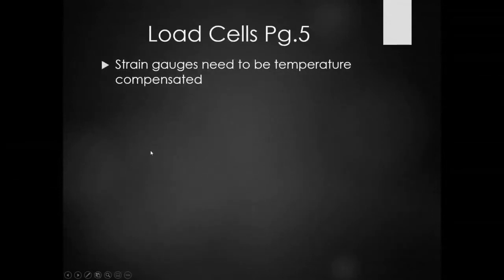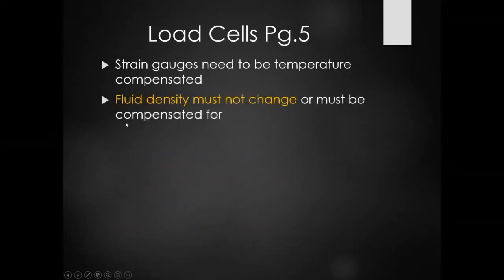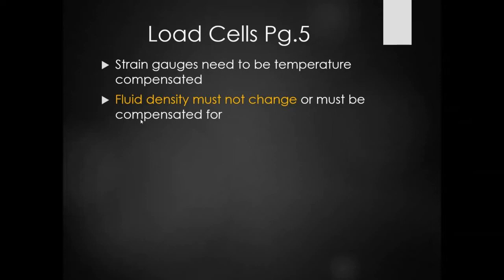Strain gauges, like most resistance-type devices, need to be temperature compensated. The fluid density must not change — this is pretty critical. If we're filling a vessel and the fluid becomes lighter, the level would have to be higher to make the same reading, and if the density were higher, the level would have to be lower. So we have to be sure the density of the process medium doesn't change, or it's compensated for, whether using a density transmitter in conjunction or otherwise.